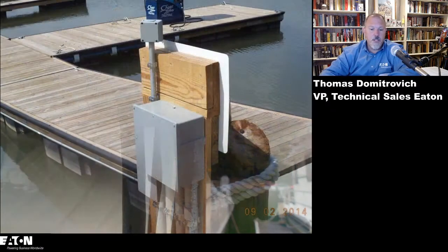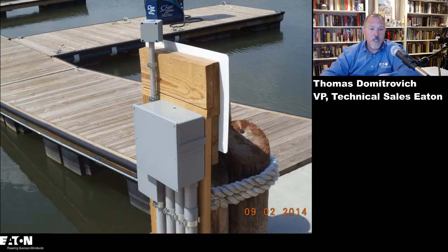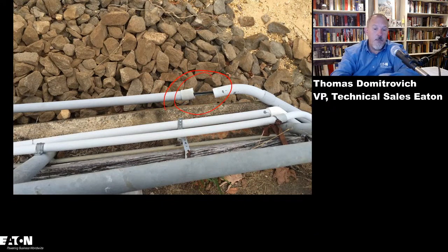These solutions were listed and they were good up until the code made changes. But there's no proper fittings on some of this stuff. You've got to think about, here's a nice installation. I can't remember what this was here for the life of me. But in that same installation, as I walk around, I'm seeing conduit raceway that's been pulled apart. In this case, this was a raceway, and that's metal, and you think things are moving, and that's going to chafe and rub up against those conductors, and that is how we energize docks and piers in marinas.